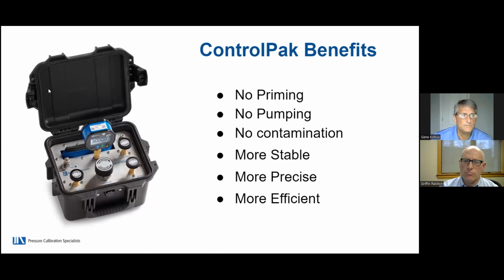ControlPak supplies smoother, more stable pressure with far less room for human error and inconsistencies compared to hand pumps. It's very easy to reach pressures from 0 to full scale, and includes all the infrastructure to do so safely. So it's also more precise, with amazing precision of the large pressure balance piston, on which you can dial to the exact pressure within 0.0005 psi. Far more precise than any hand pump.